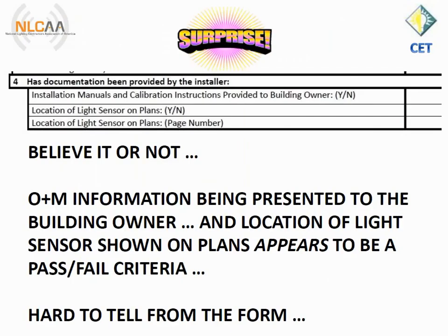As well as checking to see that the daylight zones are marked on the plans, or putting them there if they're not, a field technician is also supposed to verify that instruction and programming manuals are present on site or have been made available to the building owner.